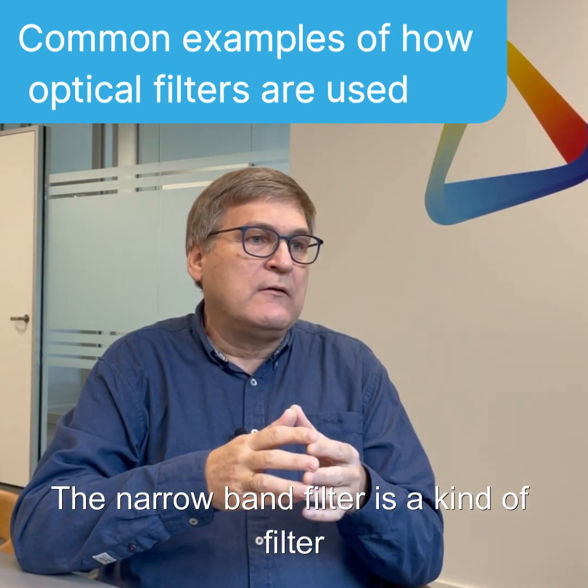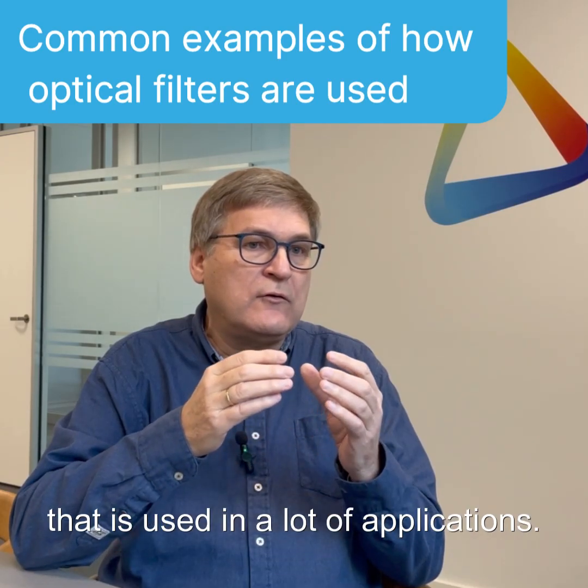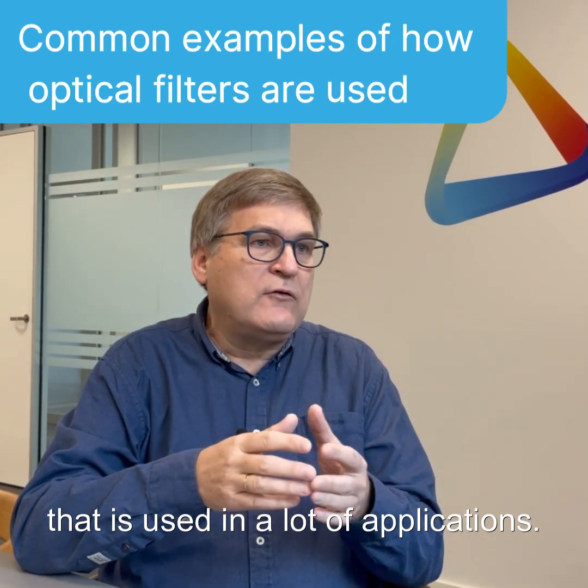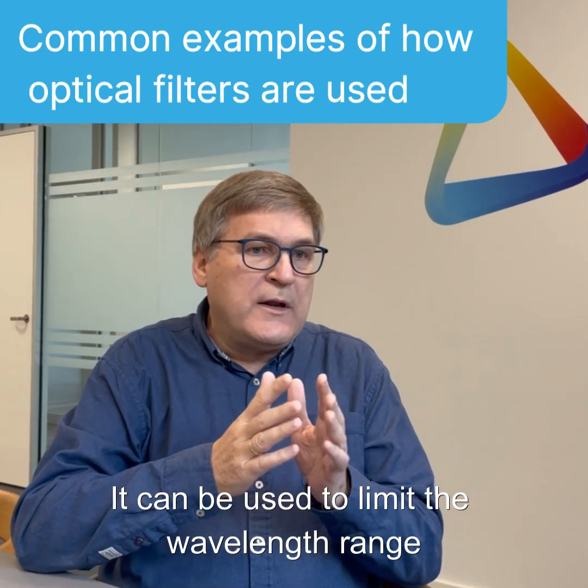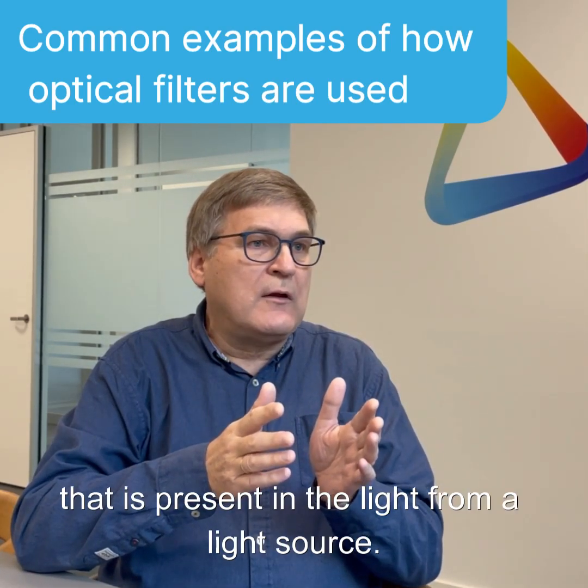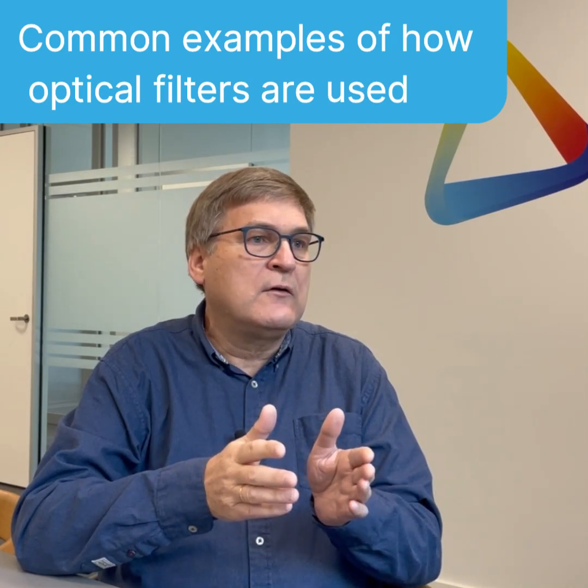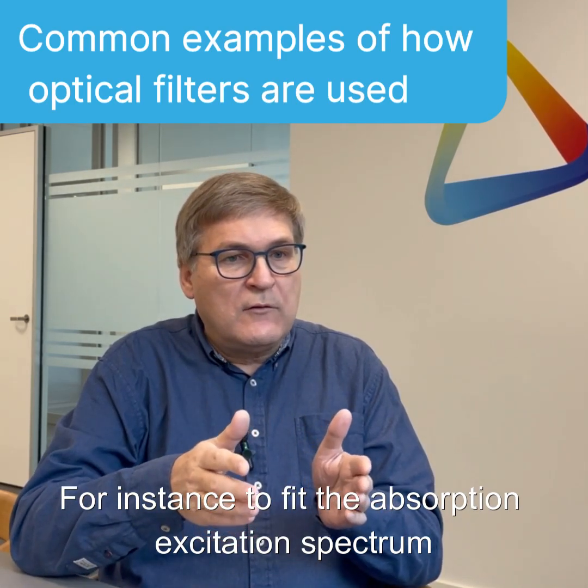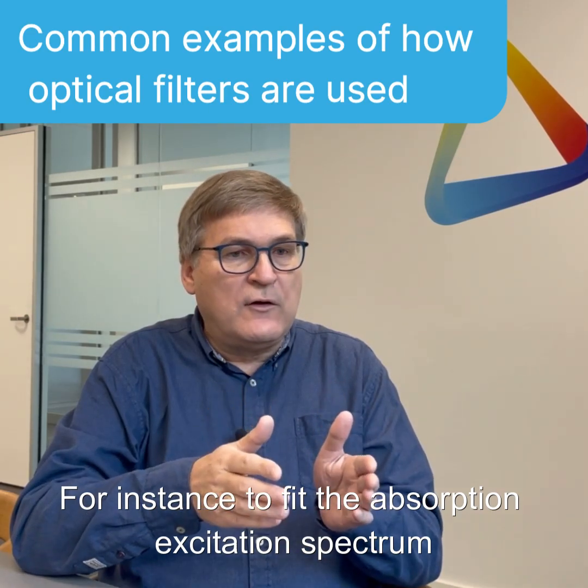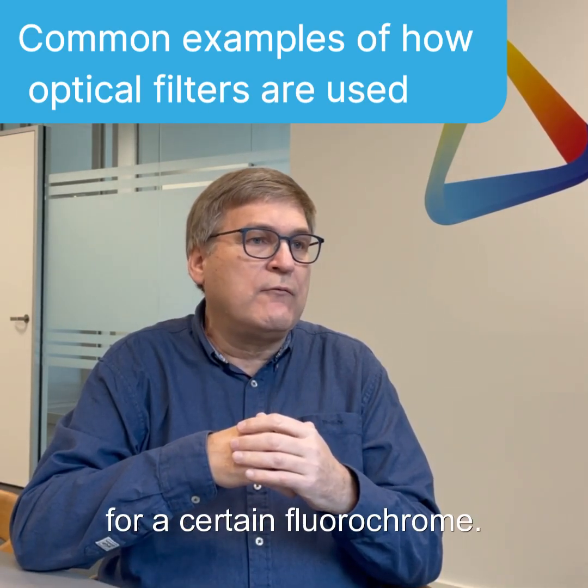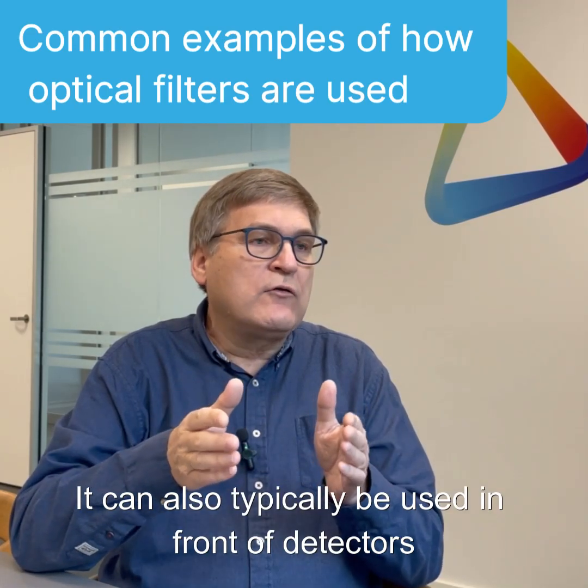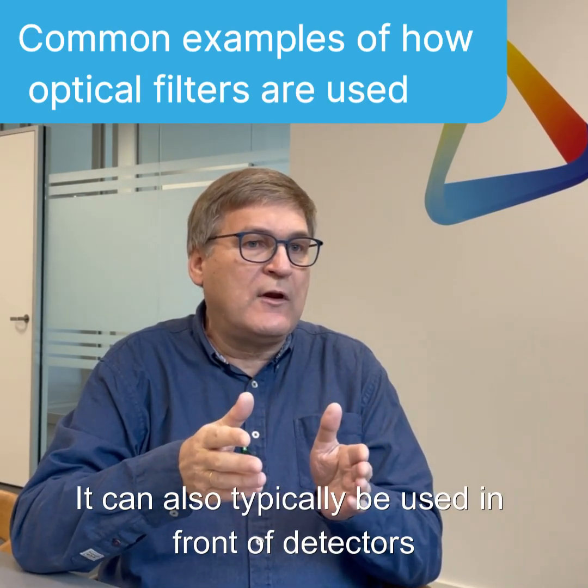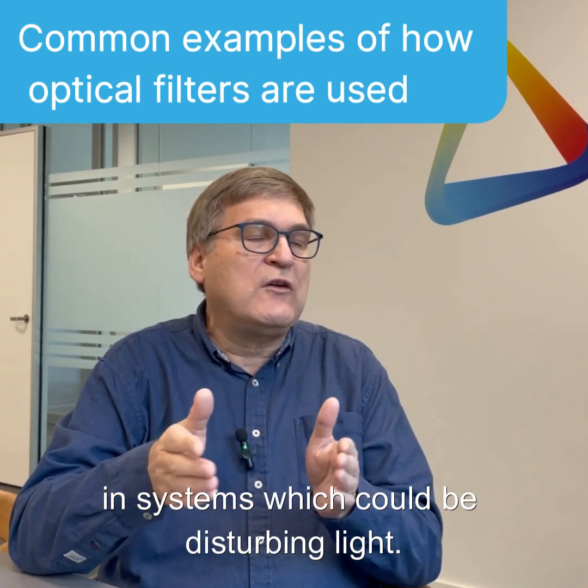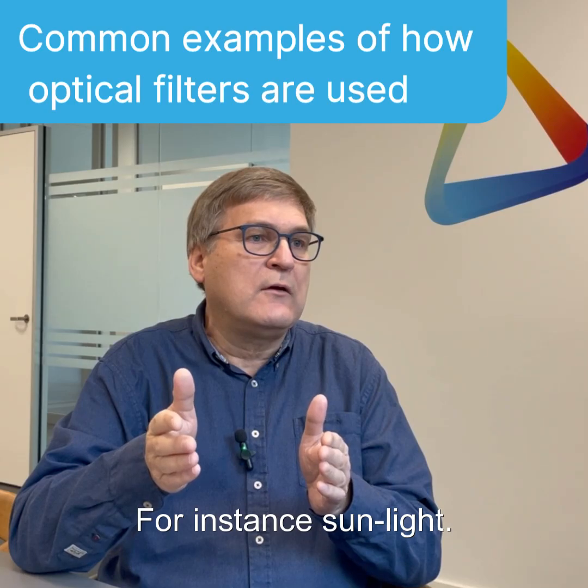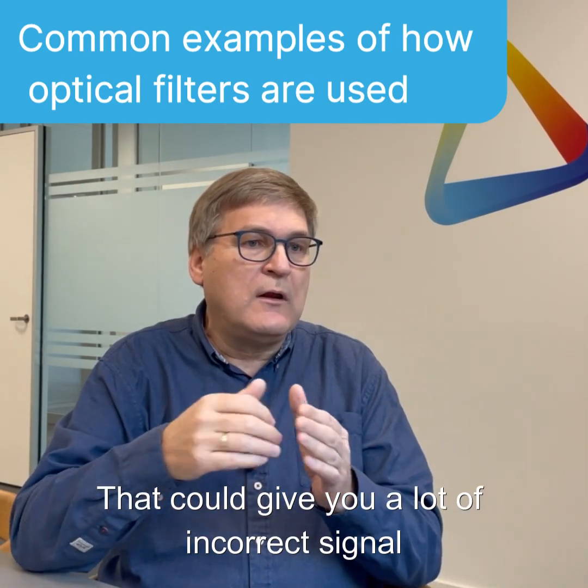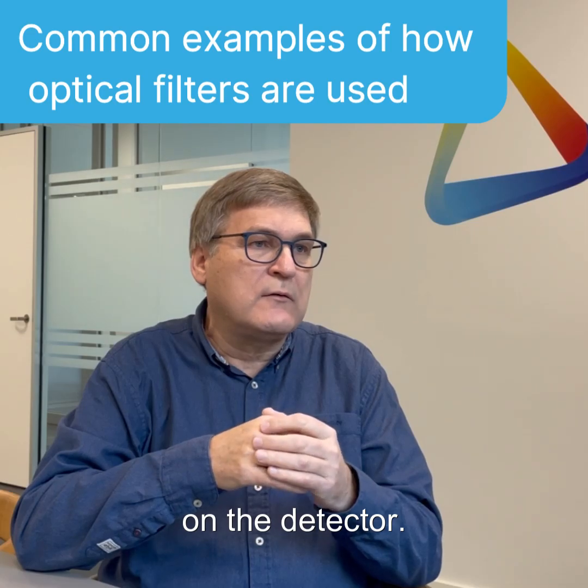The narrowband filter is a kind of filter that is used in a lot of applications. It can be used to limit the wavelength range that is present in the light from a light source. For instance, to fit the absorption excitation spectrum for a certain fluorochrome. It can also typically be used in front of detectors in systems which could be disturbing light, for instance sunlight, that could give you a lot of incorrect signal on the detector.